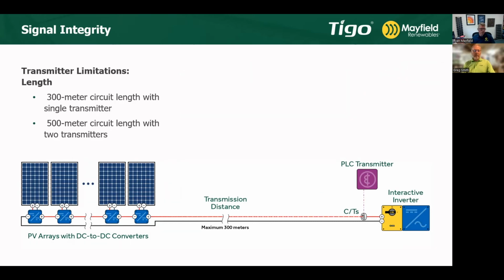One limitation on signal integrity is length. If you go greater than 300 meters, and that 300 meters is round trip, a circuit length, not one-way, that includes all your string runs, all your MLPEs, and coming back to the inverter. So as you pull the tape, call it 150 meters as you'd measure, and that would be for a single CT.